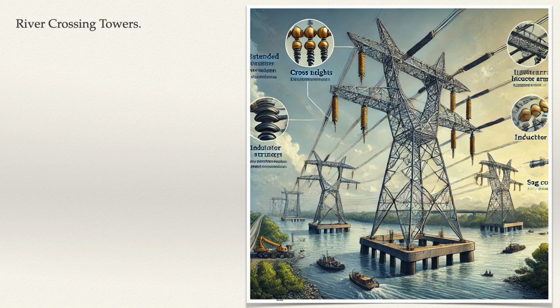River crossing towers are used for crossing rivers, large water bodies, or wide obstacles. They are taller than other types of towers to maintain safe clearance over water. They may have special designs to handle longer spans, typically 1,000 to 1,500 meters over rivers. River crossing towers provide tall structures for safe clearance and large span length.